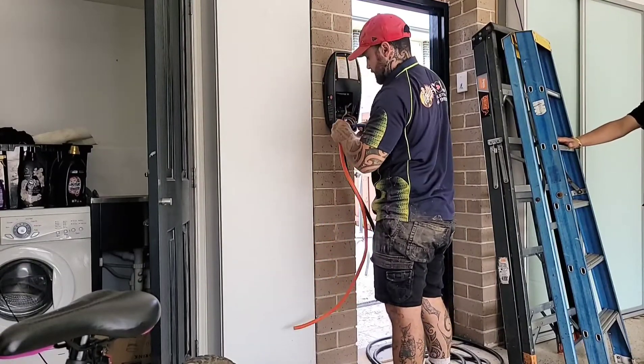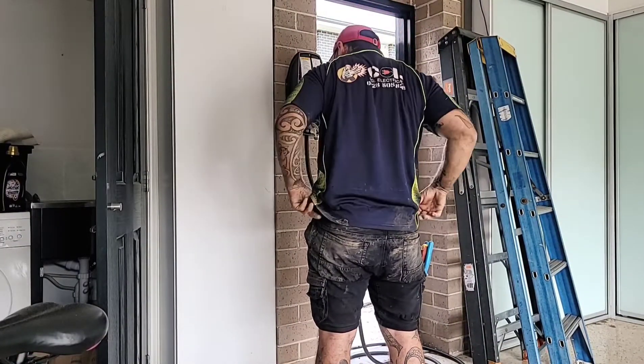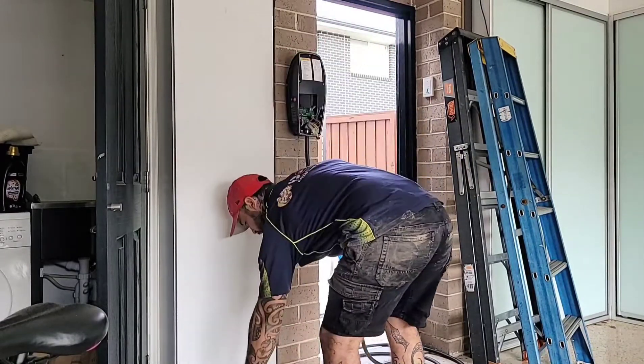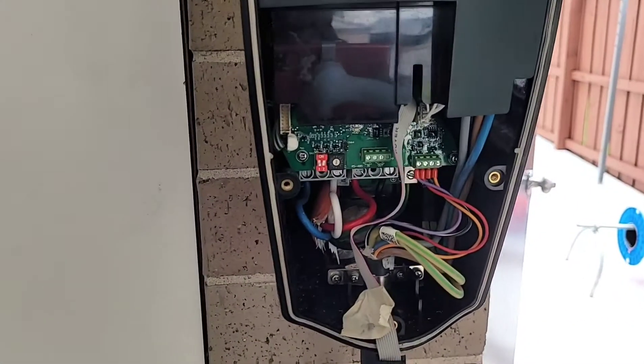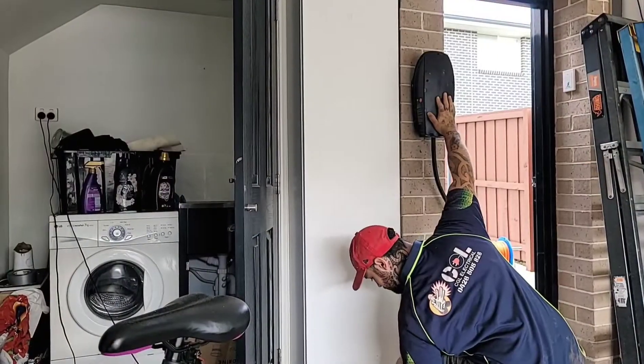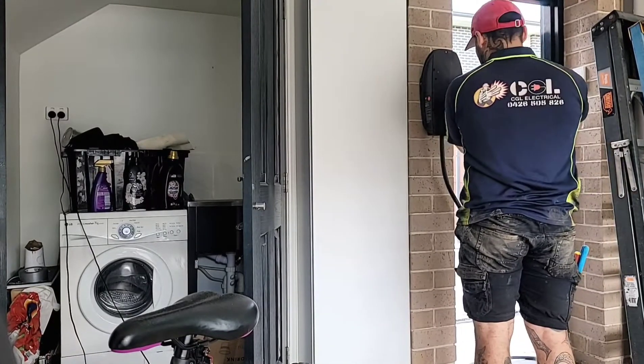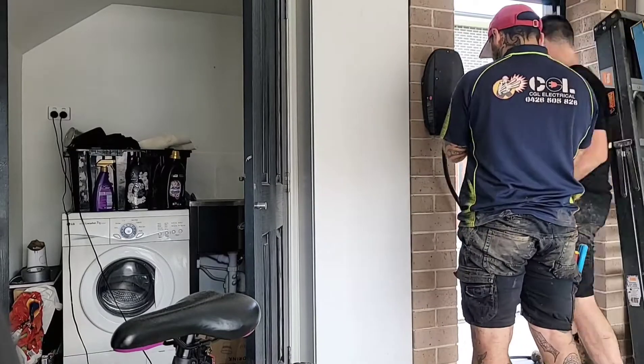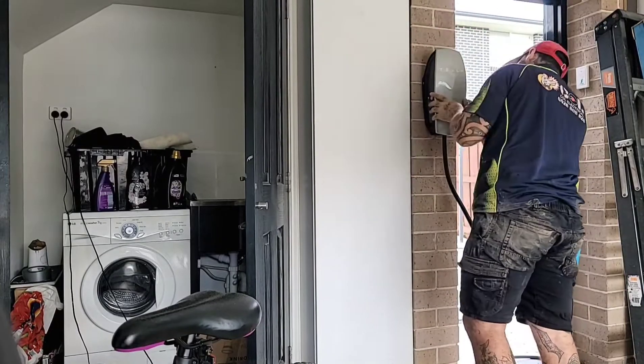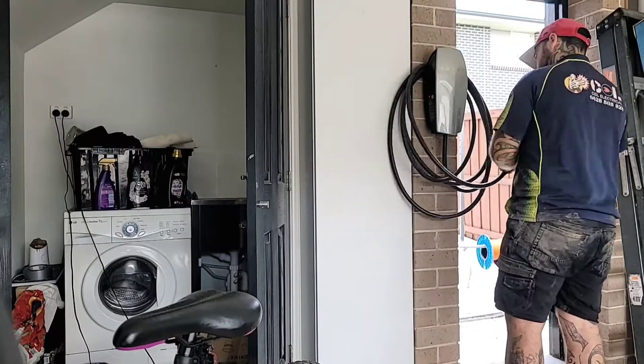We match our red A-phase to L1, white B-phase to L2, blue C-phase to L3, neutral into neutral, and earth into earth. Then we set the dip switches to the settings we want. We put the face plate back on, add the six security torque screws to the front, clip the face plate back on, and add the security torque screw back into the bottom. That is the installation of the actual charging unit complete.